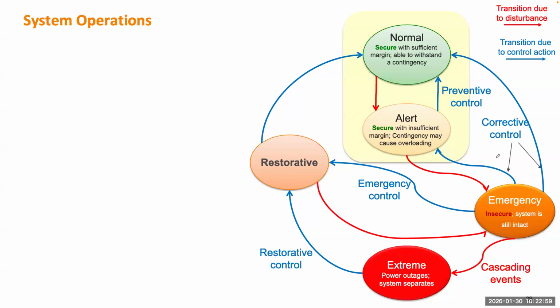Let's talk more about power system operations. A real power system can operate in the normal condition, which means nothing happened and the system is secure enough. By secure enough, I mean it meets all the standards, and it also has sufficient margin away from the boundary of reliability. So even if you have a contingency happening on the system, it is still secure. It still meets all the standards.